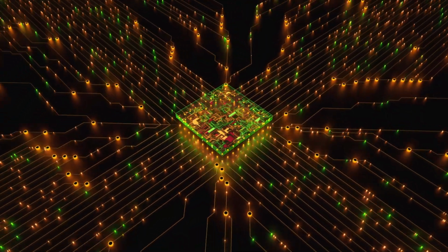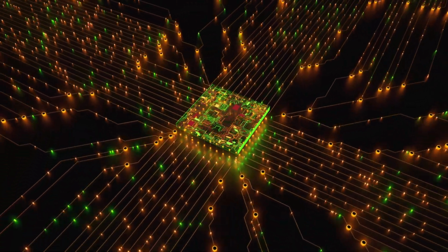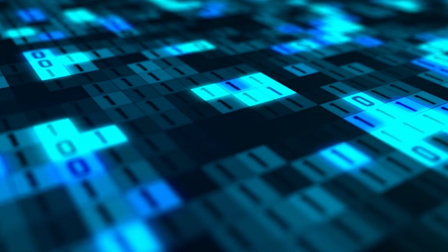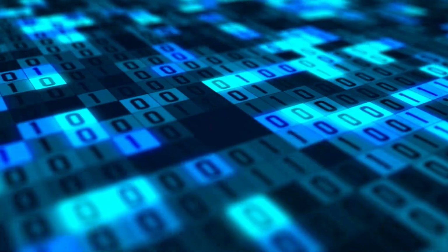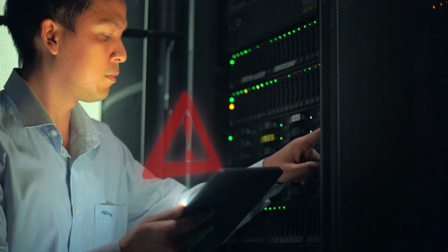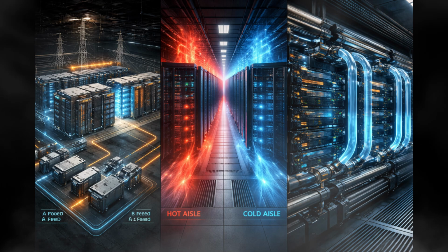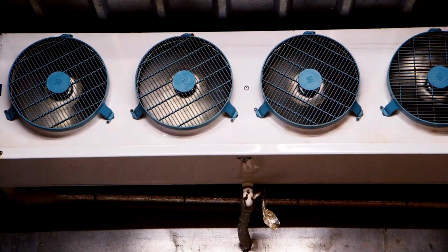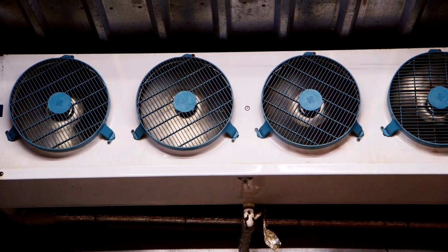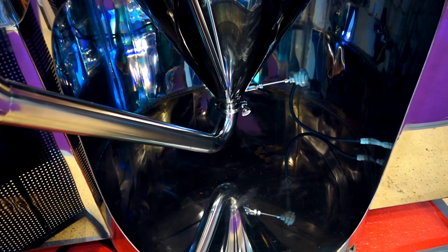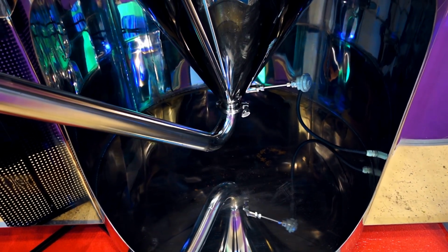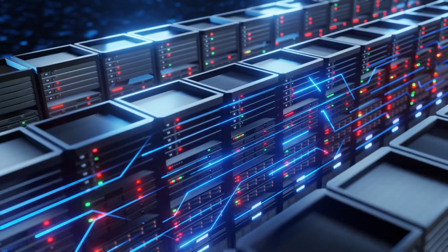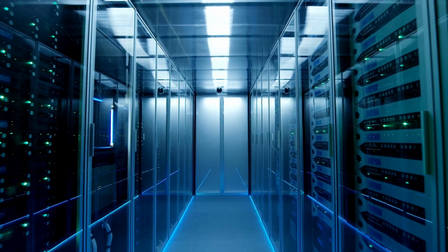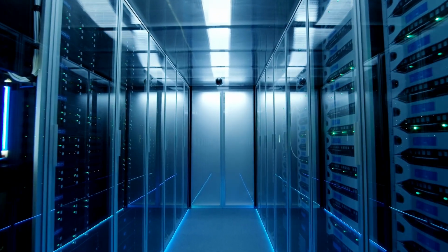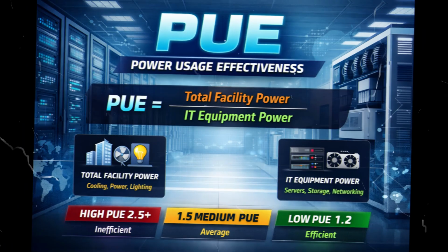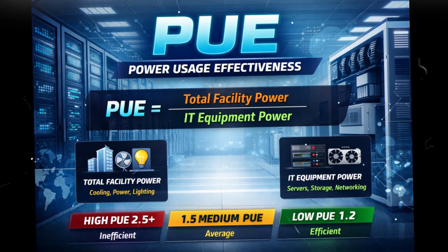Once power reaches the servers, heat becomes the enemy. Every computation produces heat, and overheating means failure. This is why server racks are arranged in hot aisle and cold aisle configurations. Cold air is pushed through the front of servers, heat exits from the back, and massive cooling systems, sometimes liquid-based, remove this heat from the building. In modern hyperscale data centers, cooling efficiency is measured using metrics like PUE, because power wasted on cooling directly affects cost and scalability.